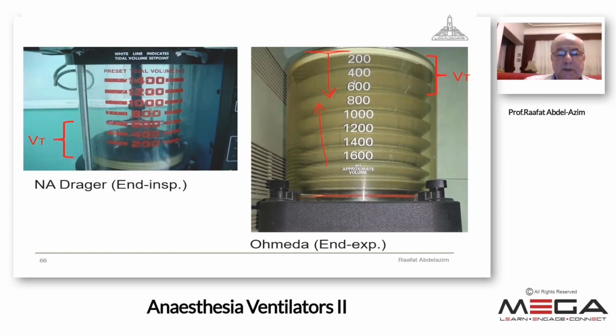This one is also an ascending bellows ventilator, but the start of inspiration is from a certain point, which is the expired tidal volume coming from the attachment, and the movement is from this point of expired tidal volume downwards. The video will explain more. So both are ascending bellows ventilators, but the starting point in Ohmeda is from the top of the chamber, and the starting point of Draeger is from the set tidal volume.